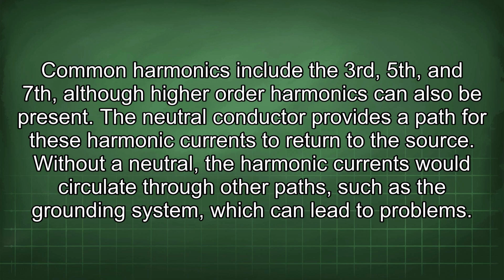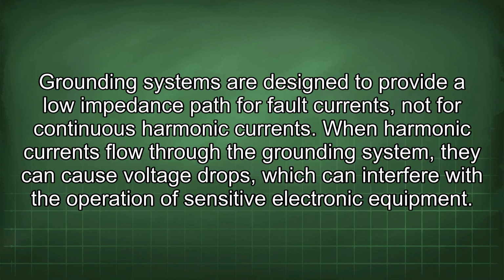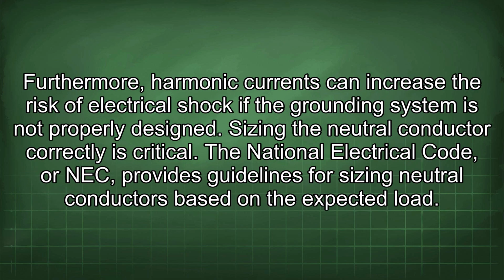Without a neutral, the harmonic currents would circulate through other paths, such as the grounding system, which can lead to problems. Grounding systems are designed to provide a low impedance path for fault currents, not for continuous harmonic currents. When harmonic currents flow through the grounding system, they can cause voltage drops, which can interfere with the operation of sensitive electronic equipment. Furthermore, harmonic currents can increase the risk of electrical shock if the grounding system is not properly designed. Sizing the neutral conductor correctly is critical.